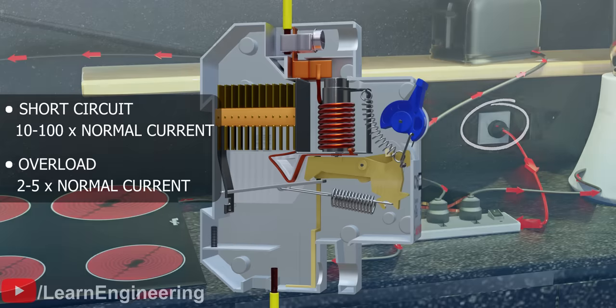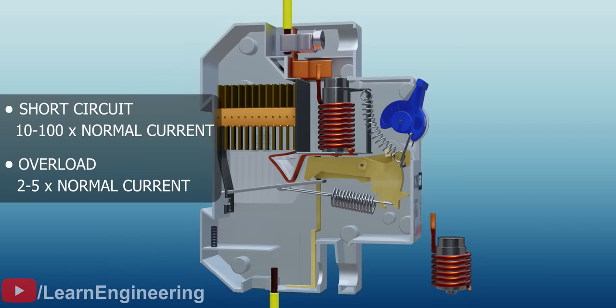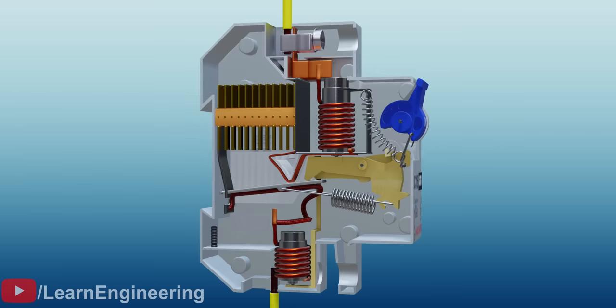You might think that use of a separate electromagnet with lesser operating rating may solve this issue, but it won't. Let's see why. The problem with this new coil for an overload condition is that it will get activated even if you simply start another electrical appliance.